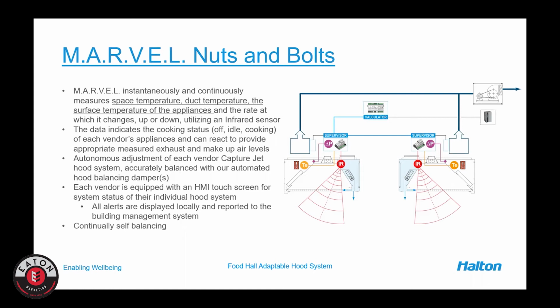We have UL listed approved dampers at each hood that allow us to modulate both the damper position as well as the fan speed for that individual hood, and maintain either an off, full on, or idle condition at that hood based on what's going on under it. We utilize infrared index cooking sensors to detect cooking activity under the canopy. The infrared sensors are sighted to the actual cooking equipment, and we're looking for temperature fluctuations, so temperatures up or down.